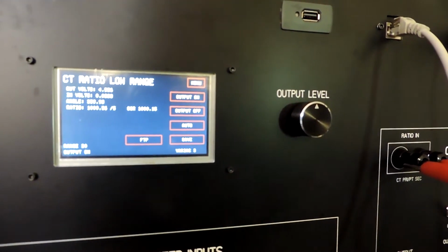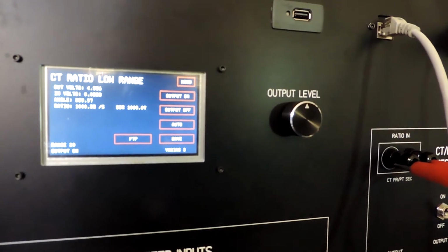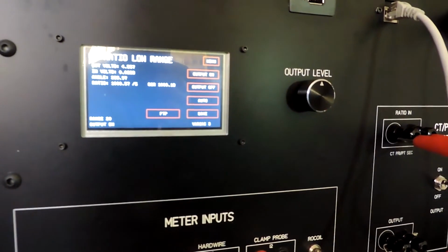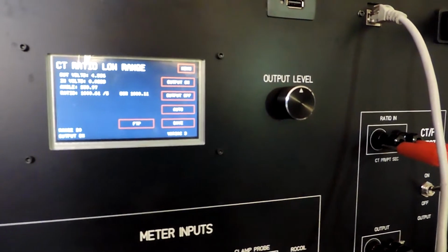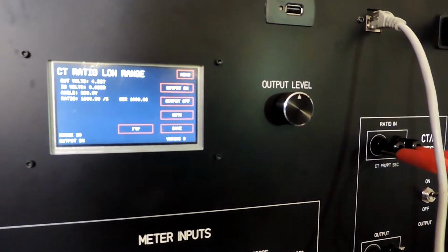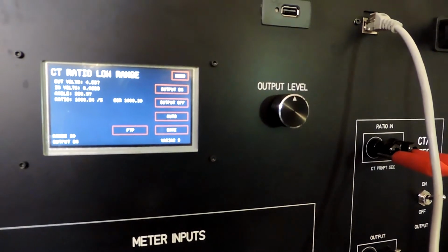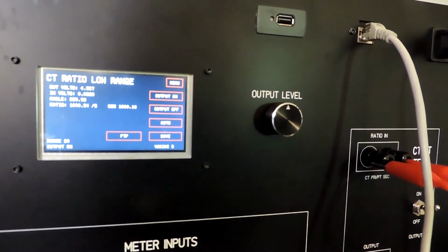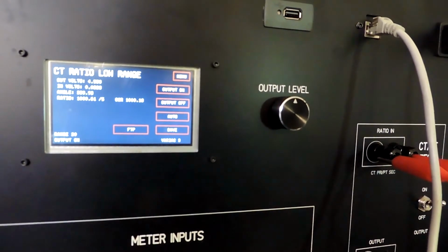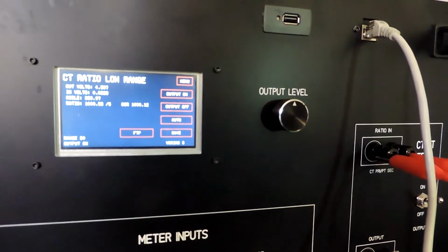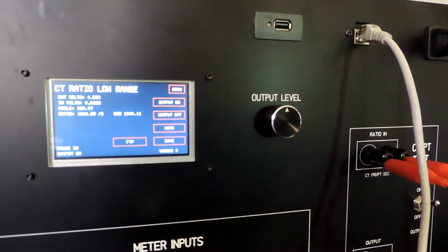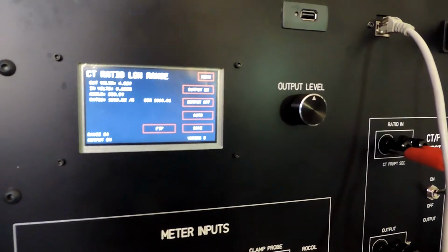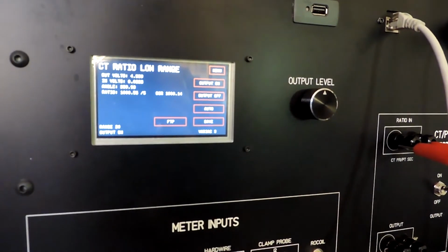1,000.58. It's already 0.05% off, so if you're talking about a 0.05% test set, that would be big, but the corrected ratio is still within 1/10 of ratio or so. Once again, it jumps around a little because the trig functions change a lot with small angles at that point, but that is wire resistance, winding resistance, and test lead resistance compensation that gets you to the exact ratio.